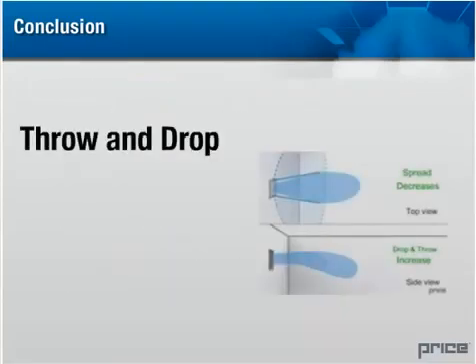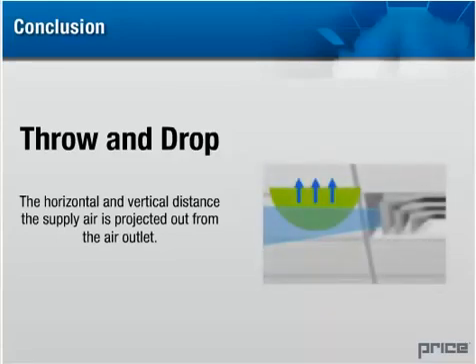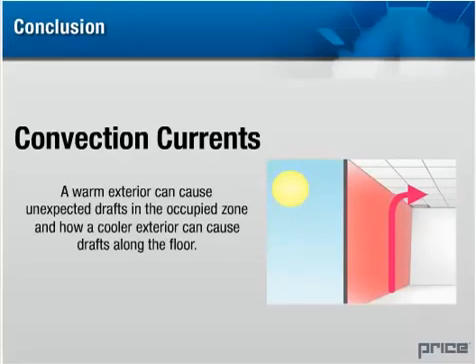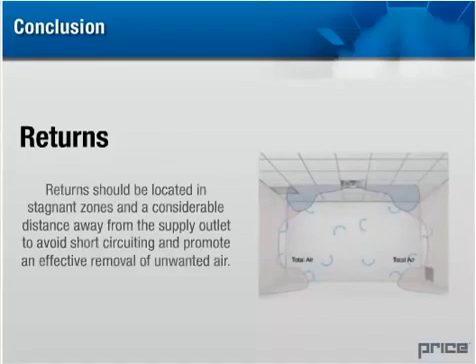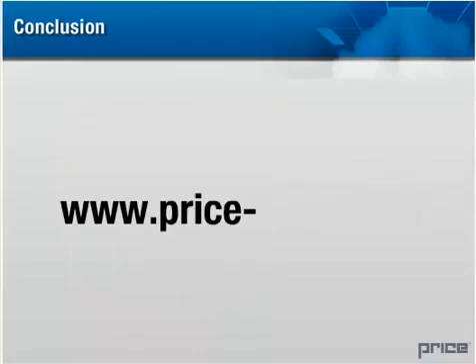We've also looked at throw and drop — the horizontal and vertical distances the supply air is projected from the air outlet — and how spread and surface effect influence them. We touched on convection currents and how a warmer exterior can cause unexpected drafts in the occupied zone, while a cooler exterior can cause drafts along the floor. Finally, returns should be located in stagnant zones and well away from the supply outlet to avoid short circuiting. For more detail, refer to the air outlet selection section, the Price catalog, or visit www.price-hvac.com.